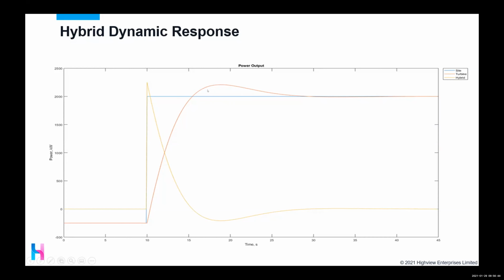Obviously that isn't an instantaneous response. The blue line here is the instantaneous response. Using the flywheels, ultracapacitors, and the load bank, we can shape the overall response such that it does match this blue trend. When called, the ultracapacitors and flywheels immediately release energy, and this begins to dissipate as they run out of juice. This is controlled in such a way as to create the necessary surplus to make this a straight step change and a flat line. When the power falls below zero, the load bank now comes in and takes load off the power output, which negates this overshoot. So the net effect is a flat 2 megawatts.